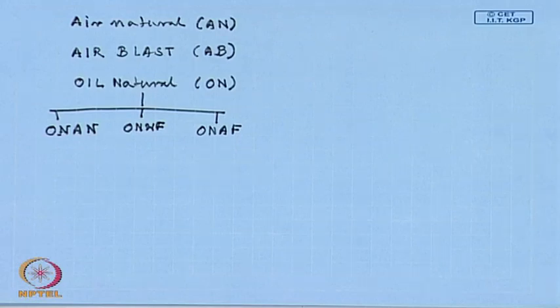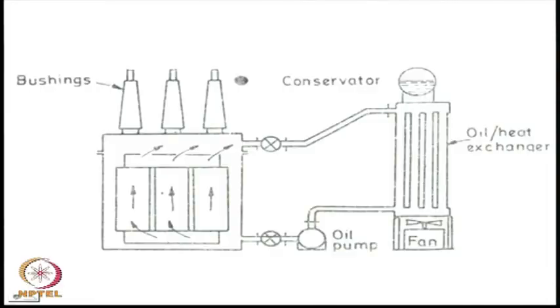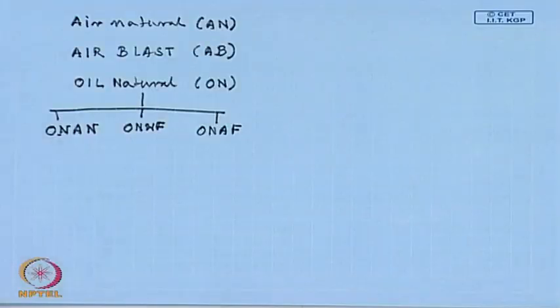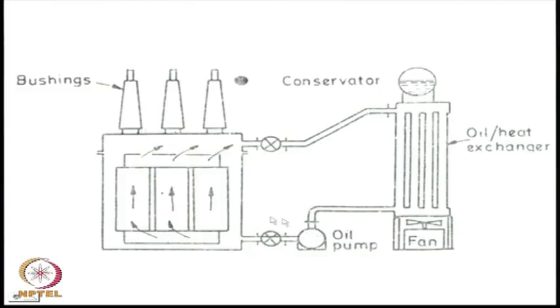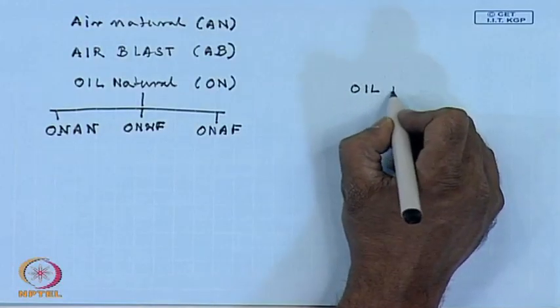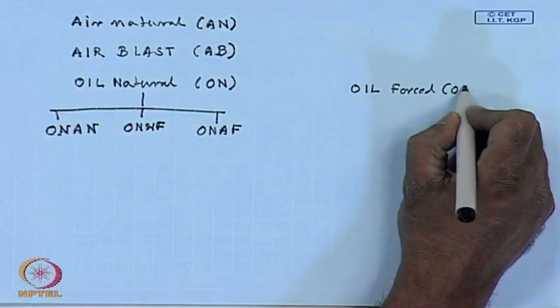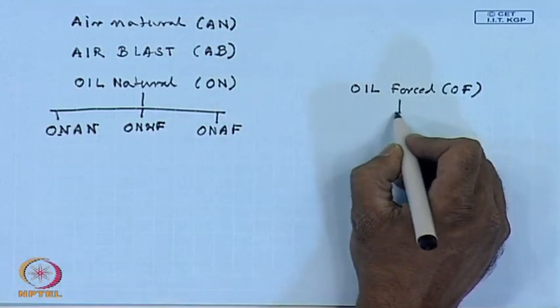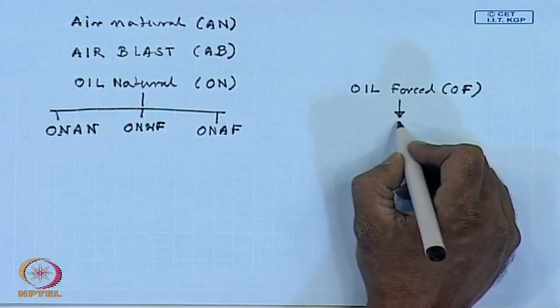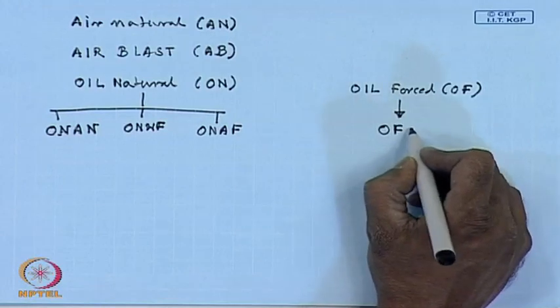For even larger transformers, the normal thermal head of a transformer is not sufficient to provide enough cooling. Therefore, the oil is circulated through the transformer by using an oil pump. The rest can be similar to oil natural air forced. So, this oil pump circulates the cooling oil through the transformer at a given flow rate in order to remove the heat generated from the transformer faster. This is called the oil forced cooling method. The oil forced cooling method is usually used with a heat exchanger which is cooled by a fan. So, the complete scheme will be known as oil forced air forced.